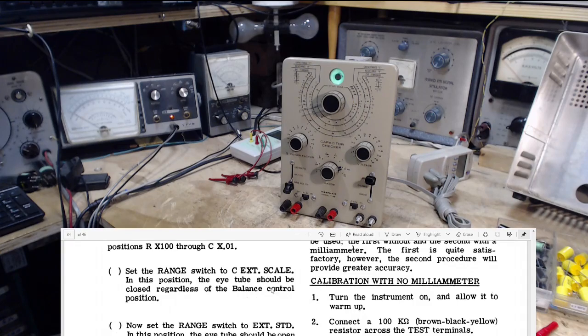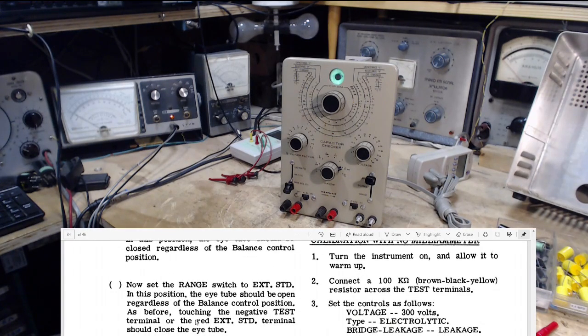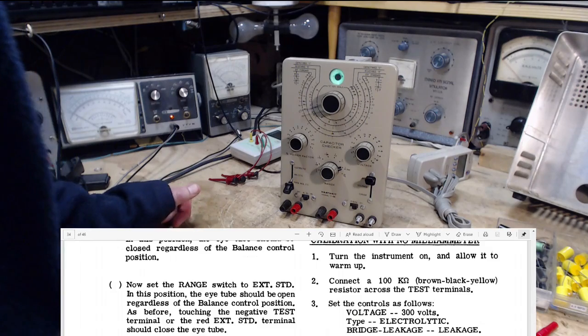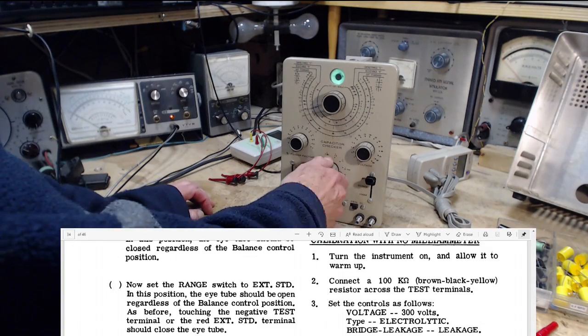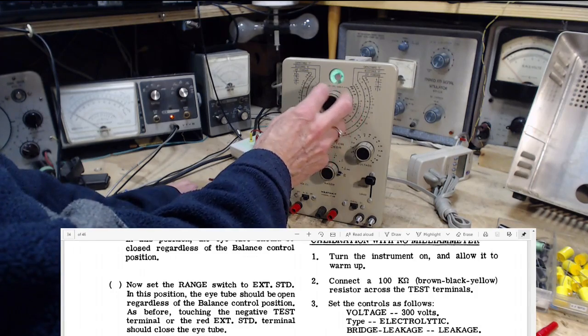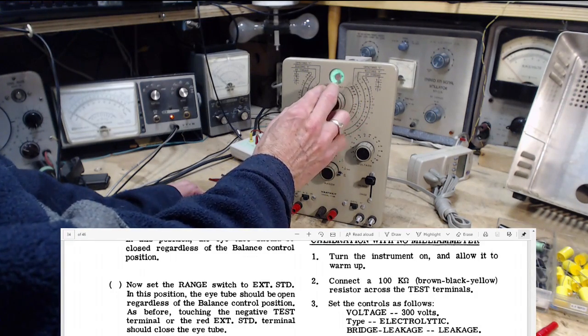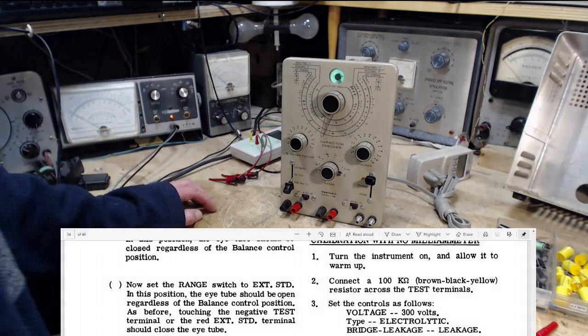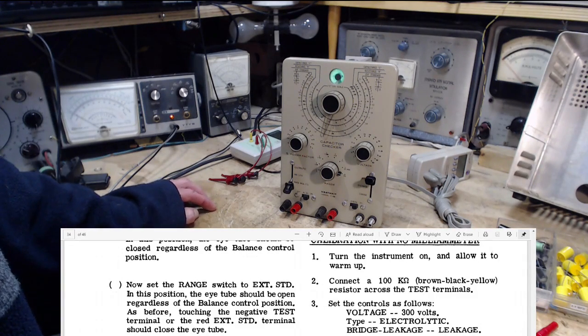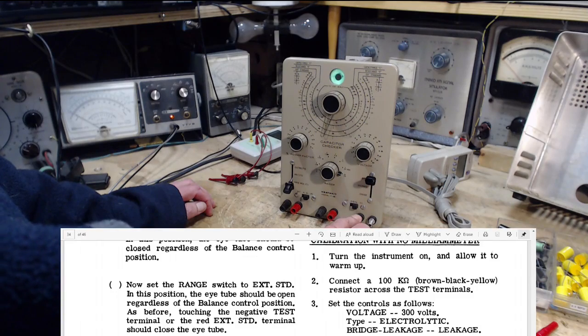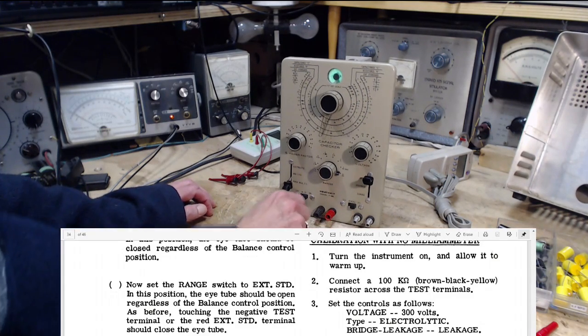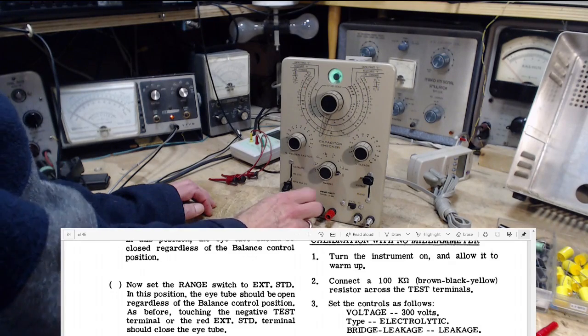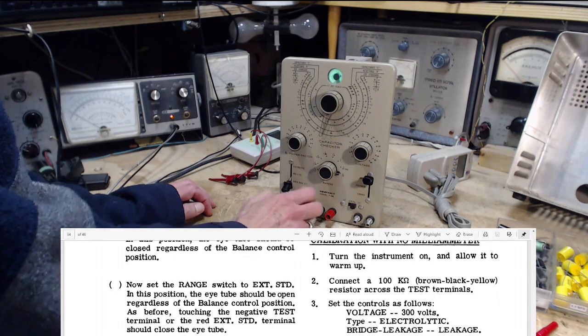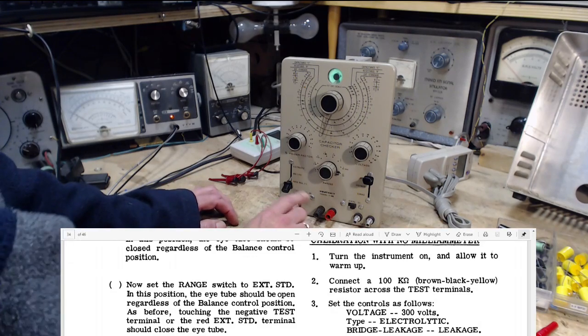Now set the range switch to external standard. In this position, the eye should be open regardless of the position. It's moving a bit, but it's open. As before, touching the negative test terminal or the red external standard terminal should close the eye. Yes, it does. External standard is here. It said red, right? The red external standard. Same thing.